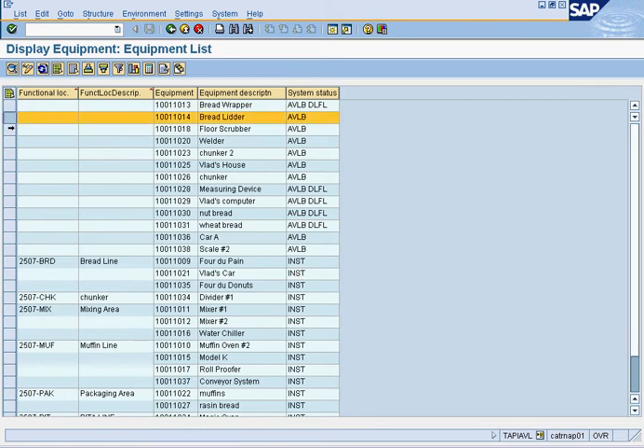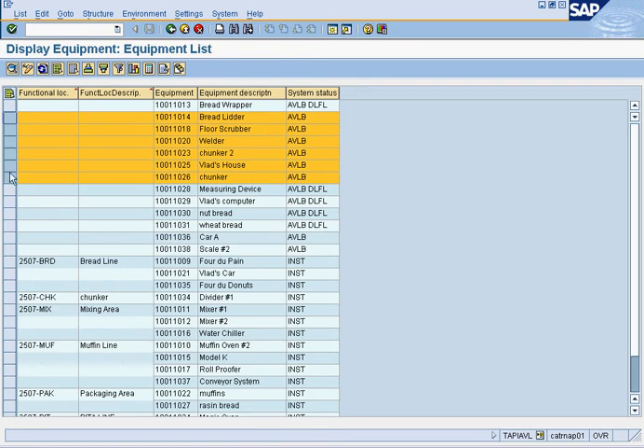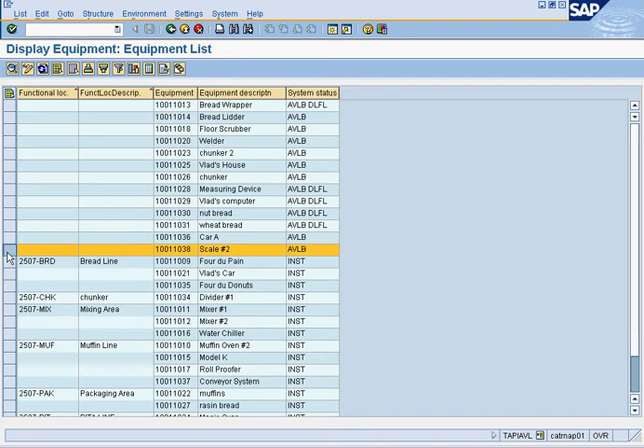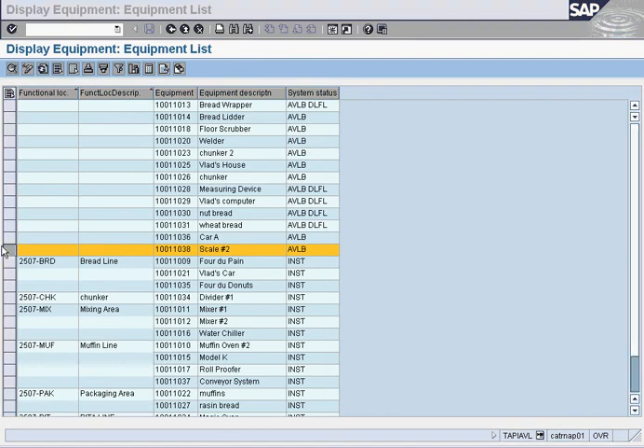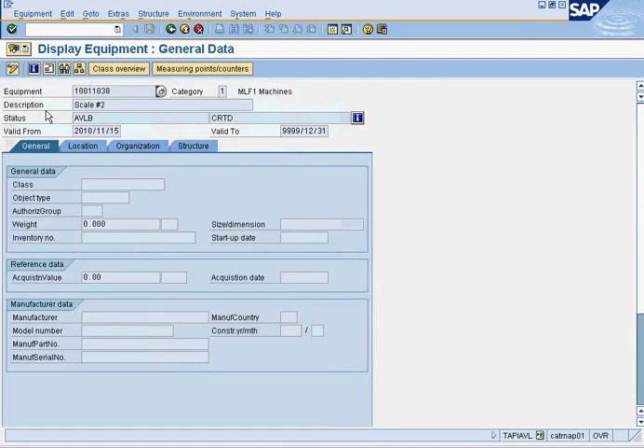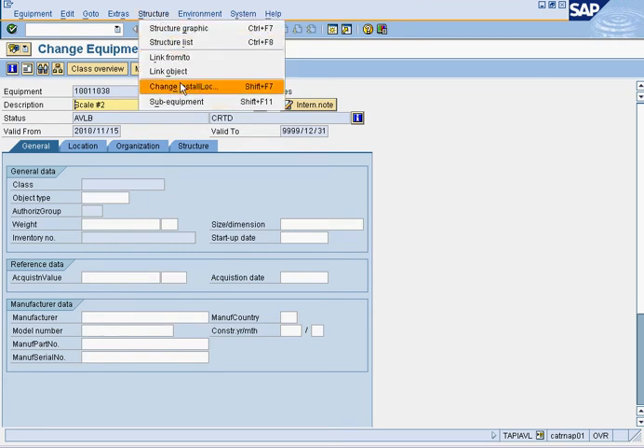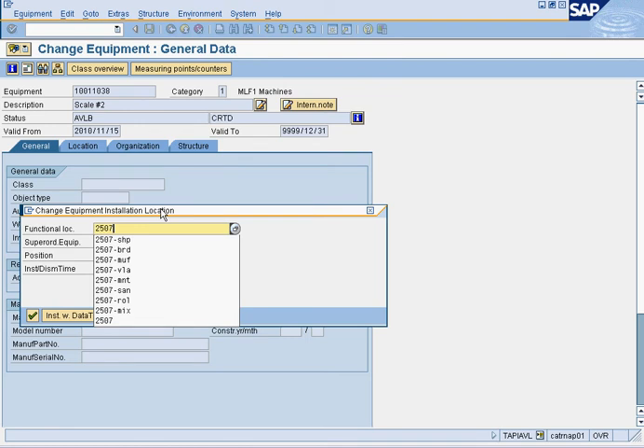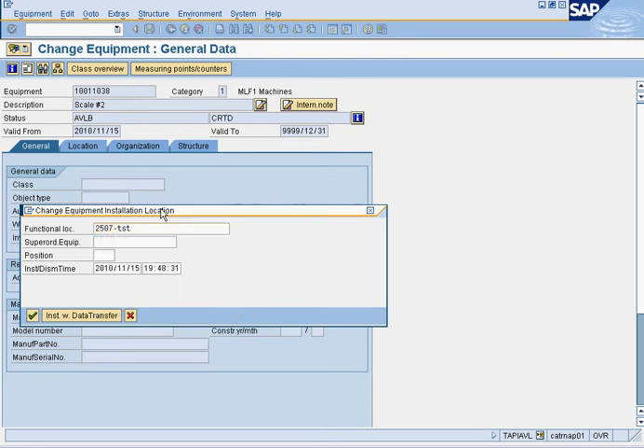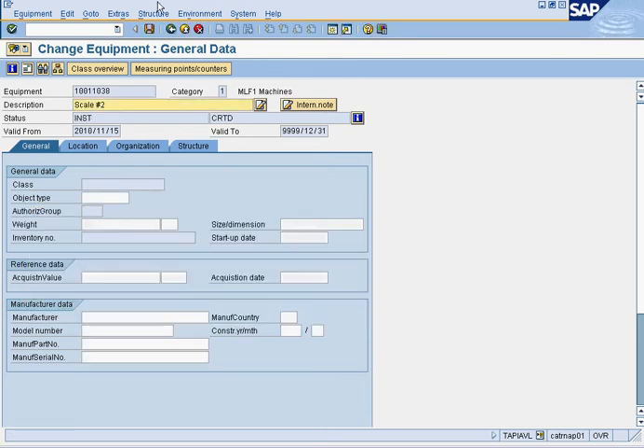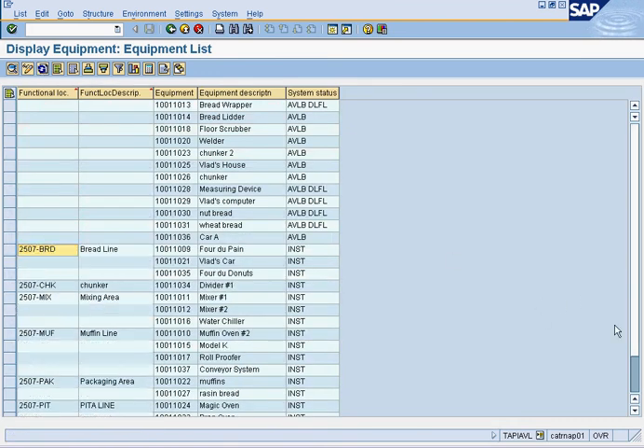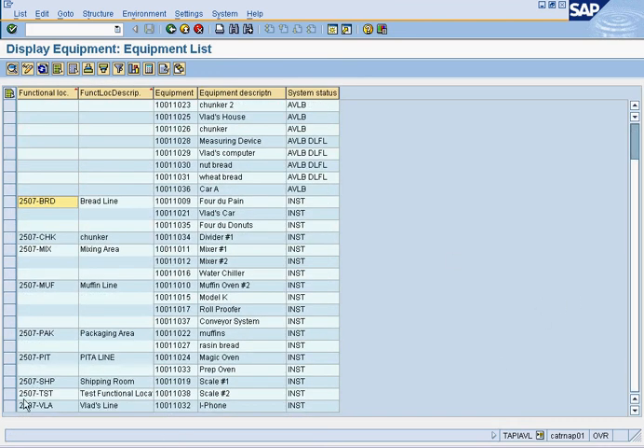Available means it's ready to be used. DLFL means it's been deleted, and INST means it's been installed somewhere within the plant. From here, we can take equipment that is available and install it somewhere. For example, the scale we just dismantled from the shipping area — click on the scale, press the pencil to make changes, go to structure, change install location, install it into the test functional location, press enter, save, refresh — and now the scale is in the test functional location.